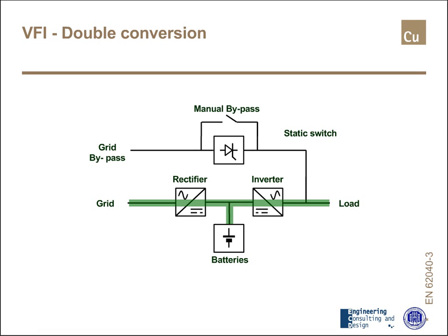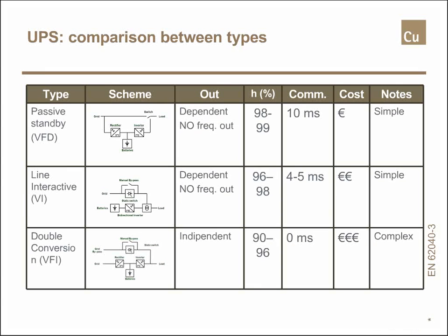From this double conversion comes the name of the class. Without the network, energy is provided to the load by batteries. In comparison with the first scheme, we can see immediately that we do not have to switch anything when moving from grid operation to battery operation. In this table, I tried to compare these three main types of UPSs.